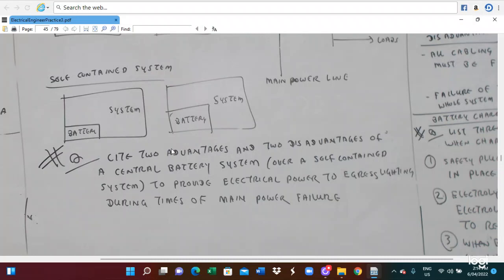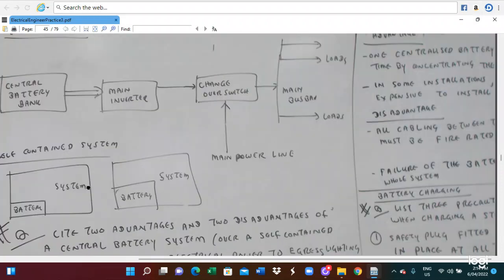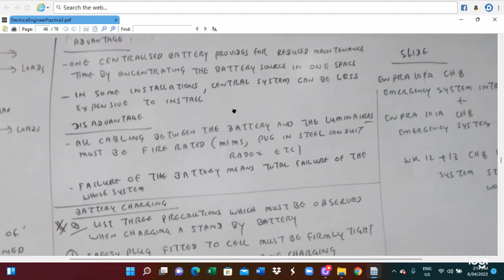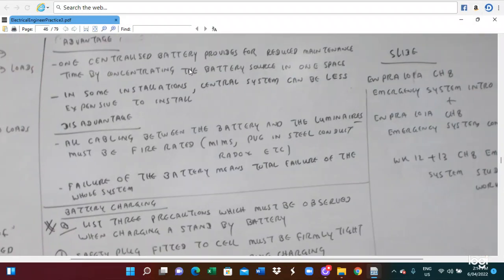The purpose is to provide electrical power to the egress and lighting during a main power failure. So in this case, the advantage is that one centralized battery provides for reduced maintenance time, concentrating the battery source in one space. So a centralized system is easier to maintain. In some installations, a central system can be less expensive to install.